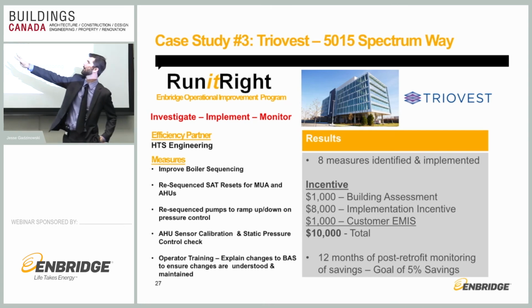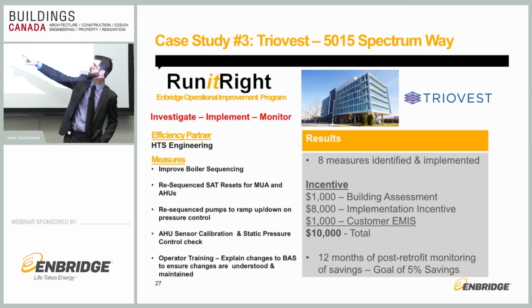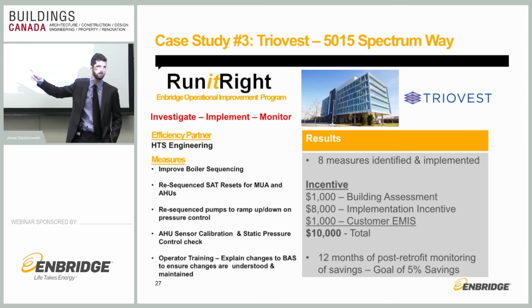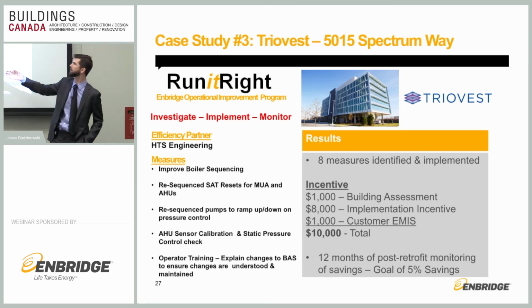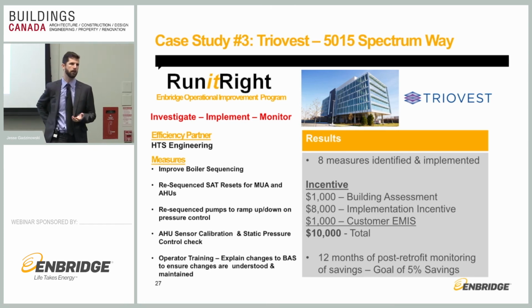So Run It Right has 3 phases. It's investigate, implement, and then monitor. So investigate, HTS did, implement the measures there, and then monitor is the verification of savings. So you can do 2 streams. We can put on a remote meter reader. We'll connect it and get pulses from your gas meter, and then we will take 12 months of data post-retrofit and then compare it to the baseline and then try to get a savings number there.